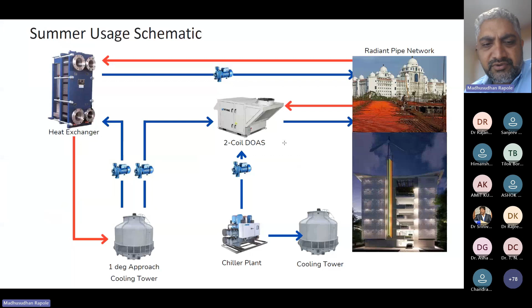This is the Telangana State Renewable Energy Department building. I'll quickly show what happens in summer. We do have a chiller because this is an office and we also need to dehumidify. We run only one chiller; the rest runs on cooling tower. What we are able to achieve is around 0.29 kilowatt per ton, which is unheard of.